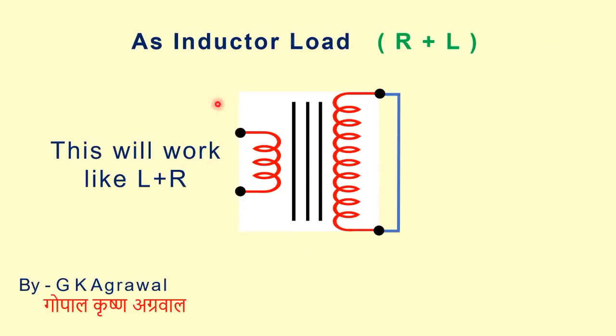Now, this has become a inductive load. Here what I have done, high voltage primary winding is shorted using a wire. A secondary low voltage winding is used as a load. This will show L plus R both. R is due to resistance of the winding wire. Better the quality of transformer, the value of R will be less.